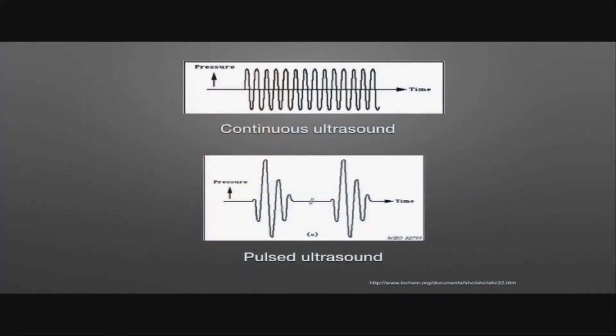Continuous ultrasound, which goes on all the time, is what we use for things like continuous wave Doppler. But for things like B-mode imaging or M-mode imaging, we're going to be using pulses of ultrasound. These pulses are short collections of ultrasound waves which are sent out, and the overall time of this pulsed ultrasound is known as the pulse duration.